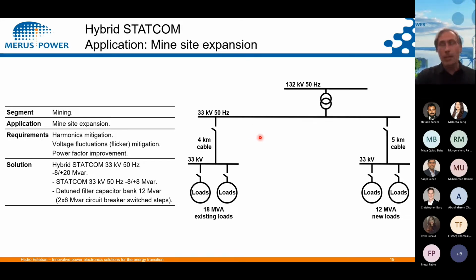And if the mine operations are pretty big, we need to be able to comply with the grid code regulations of a certain country at the point of common coupling with the main network. So in this case, typical things are harmonics mitigation, because variable speed drives, especially the big ones, generate a lot of harmonics during operation. There can be flicker, because we have all these dynamic loads operating. Power factor can also be very low in these installations.